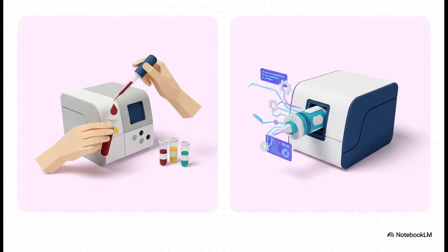Now, within the ROTEM family, you're mainly going to see two devices. The ROTEM Delta is the workhorse that many of us grew up with. It's a fantastic 4-channel semi-automated system, but it does require you to manually pipette the blood samples and reagents. The newer ROTEM Sigma is fully automated. It uses this brilliant all-in-one cartridge system, so there's no pipetting needed, which really cuts down on the potential for human error. The really important thing, though, is that they both use the exact same core technology. So all the algorithms and treatment thresholds that were developed on the Delta can be used directly on the Sigma.